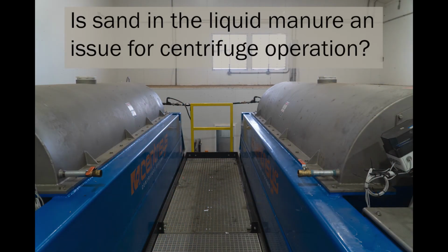When we added the second screen, we think we'll do even better. We're not going to be hammering those centrifuges as hard. Basically, a centrifuge, at the RPMs it's spinning and at the volume of water getting pushed into it, it's sanding it down. The first maintenance, we found that the inside of the centrifuge was relatively in good shape, a lot better than what we had planned. But the very end of the centrifuge where the water is hitting, it looked like somebody just sandblasted the wall in, dented it in, just wore it out. If we could control that, that would add more time onto the life of that centrifuge.